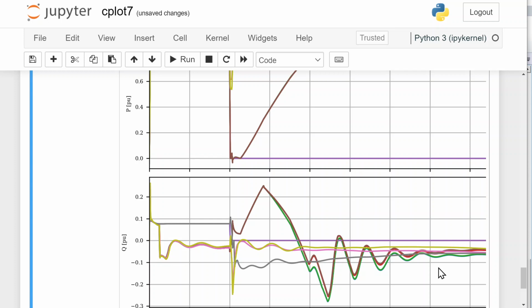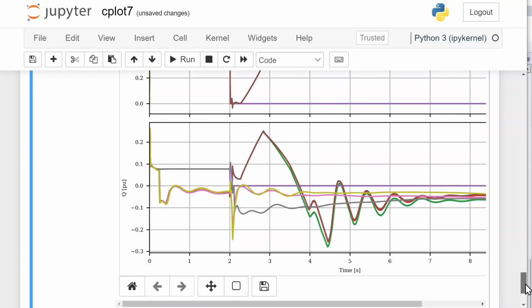If we went through the legends, we would see that with only the line to bus 4 in service, especially after the dynamics of the fault event, the plant trips. So even though the hosting capacity was predicted to be over 300 megawatts, in this case there is an issue. It could be resolved by changing control parameters, or maybe a type 4 wind turbine would do better, or we could just accept the fact that this really leaves the system in an N-2 condition, and so maybe we don't necessarily expect the plant to be able to produce output in that scenario.